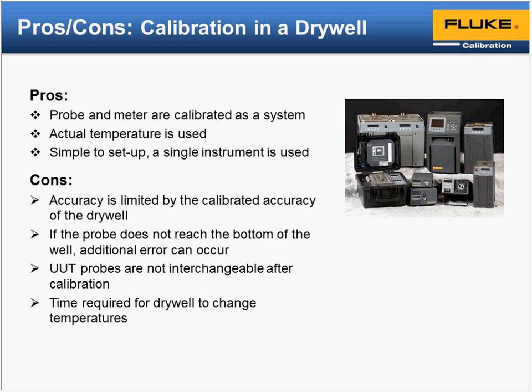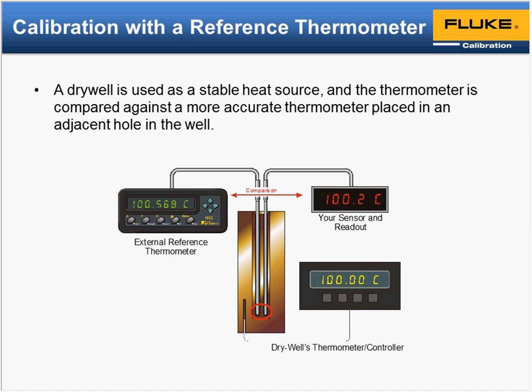We've made the adjustments. Any error that might potentially be compensated by the electronics or the probe, we've kind of nulled them out. It's not easy to say, okay, we took a quarter of a degree out of the electronics and a quarter of a degree of error out of the probe. Everything got nulled in that system setup when we made the adjustment. The other thing is, depending upon the type of well you have, there may be some additional time required to get to the various temperature points and then stabilize to take your readings or your data and adjustments.